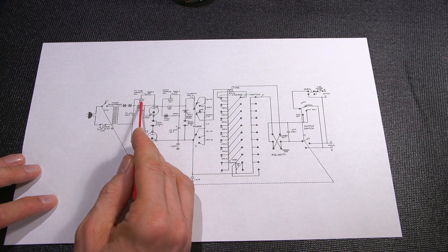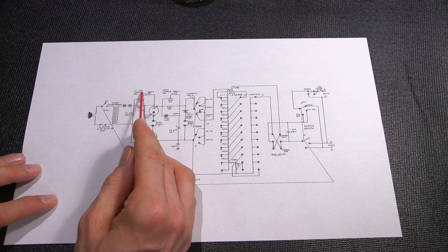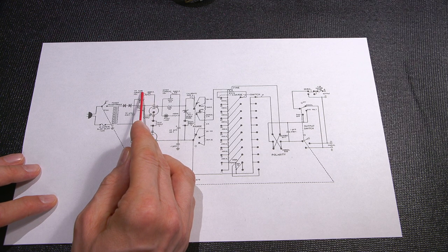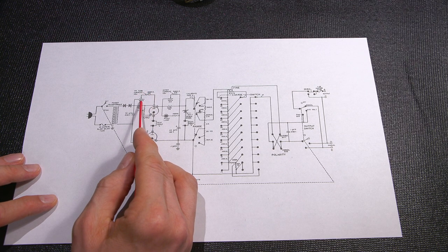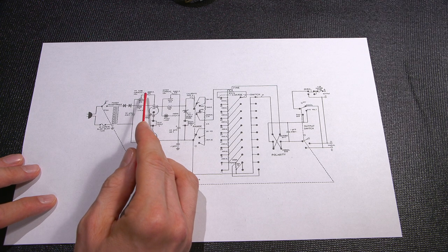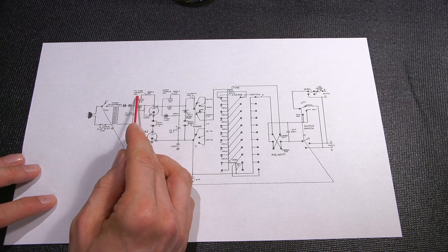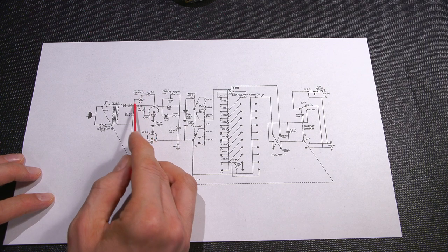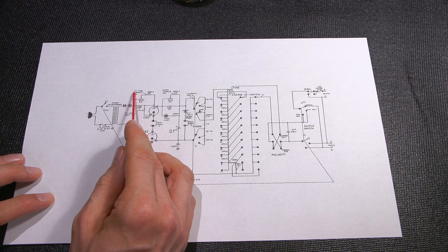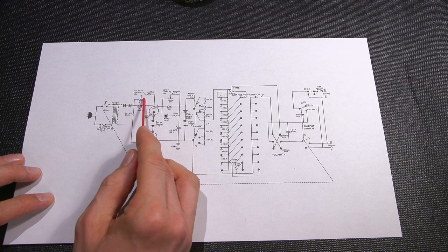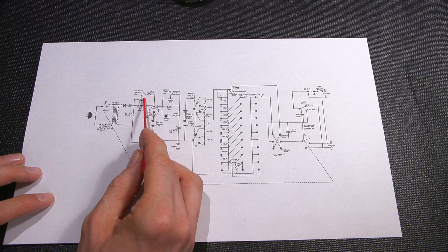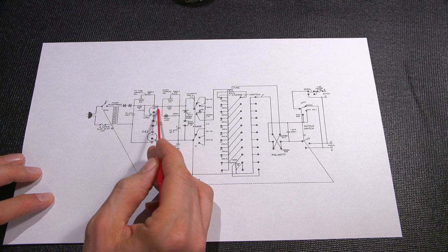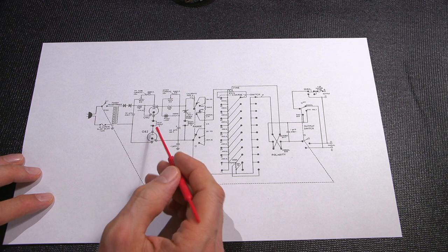Now, as you can see here, it says VR tube current adjust, and they have an arrow pointing at a fixed resistor instead of the variable resistor. Maybe a typo there. Maybe that was supposed to point down here. At any rate, this is the adjustment. So the voltage regulator current adjustment would be right here. Moving this VR back and forth would adjust the operating current of both of these regulators.